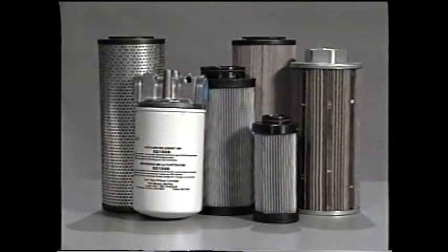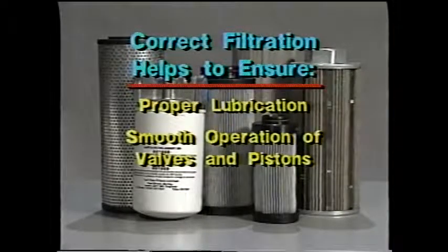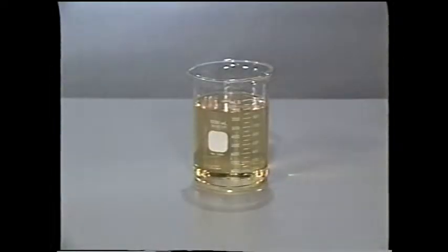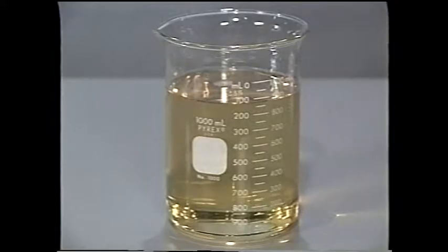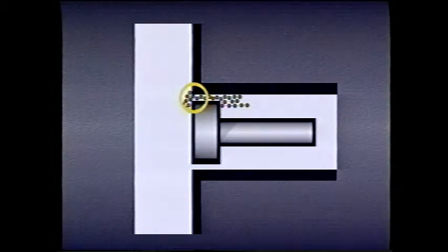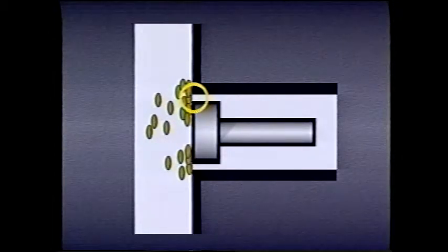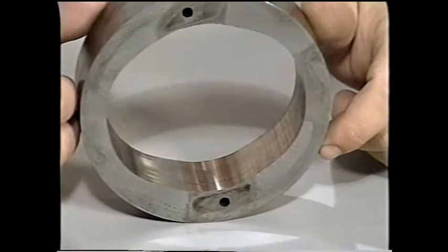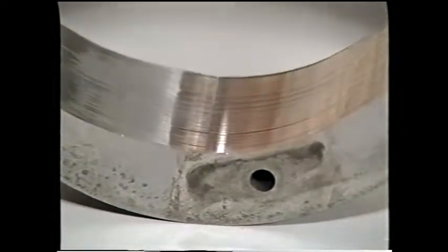All hydraulic systems today require filtration to keep their fluid clean enough for satisfactory operation. Correct filtration and careful maintenance of the filters helps ensure proper lubrication, smooth operation of valves and pistons, and a system that runs efficiently and reliably. Hydraulic fluid must be extremely clean to assure proper operation. Virtually any dirt will cause problems. Very fine particles can build up inside clearances like silt in a stream, clogging valves. Medium-sized particles can work into clearances, break down lubrication, and cause excessive wear. Large particles may actually block openings, plugging up the system. Any dirt that mixes with hydraulic fluid makes a very effective grinding compound that will cause rapid wear.